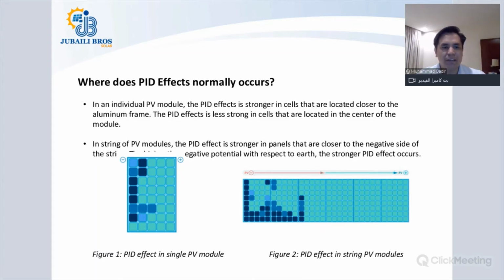Where do PID effects normally occur? Talking of one solar PV panel, and then I will speak of the whole string. If you have a solar panel on the negative side of your string, normally it gets affected by the PID, and the cells which are closer to the frame of your solar panel will get affected quicker. And by the time, if you do not cure it, the cells in the center area will also get affected. If we talk of a whole PV string, the PV modules which are on the negative pole of the PV string get affected by the PID sooner.